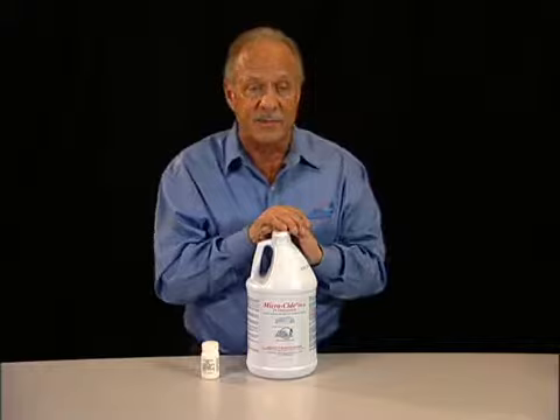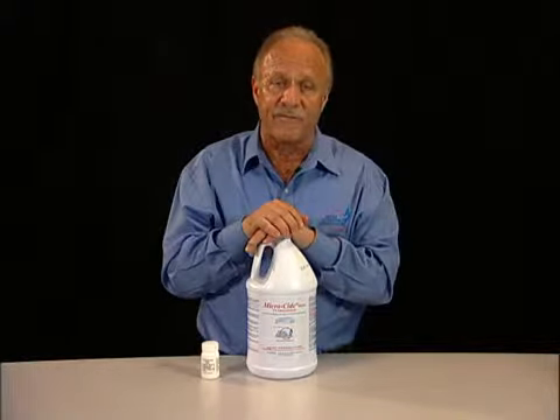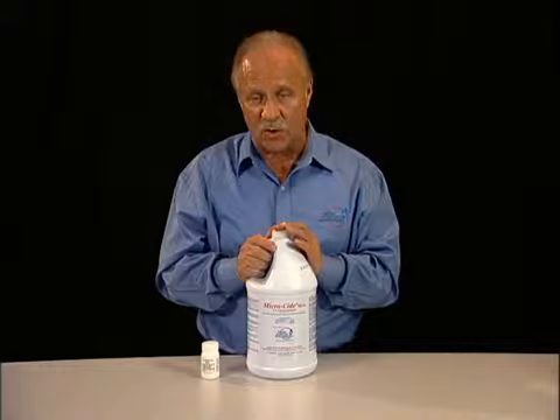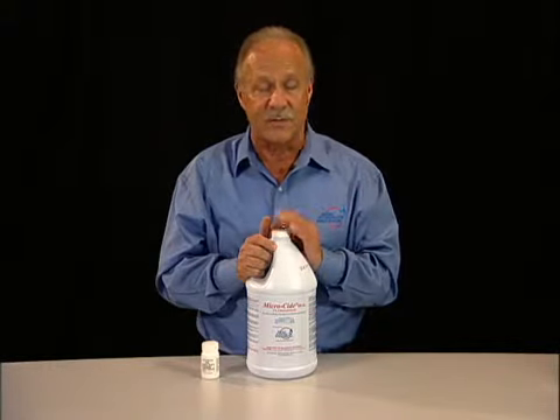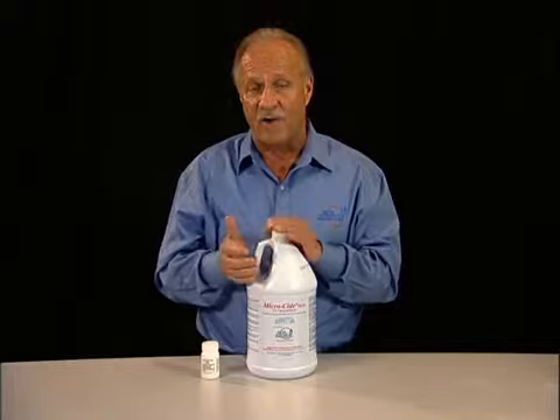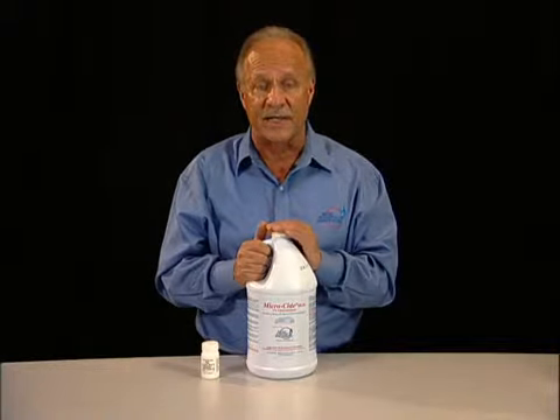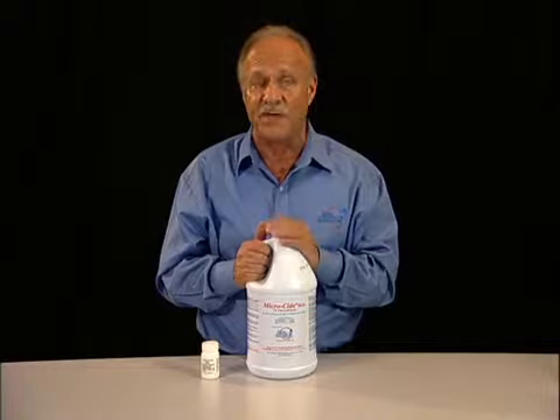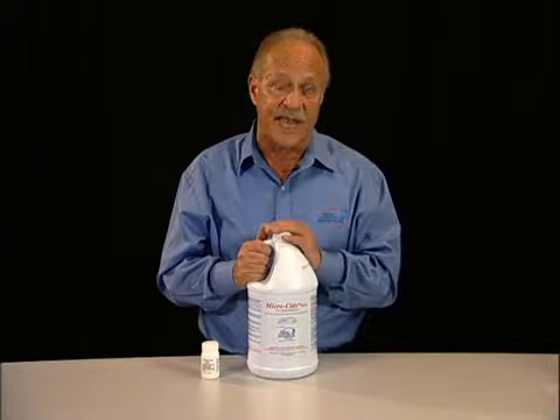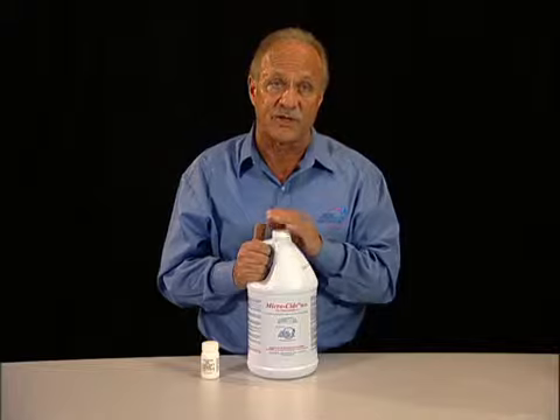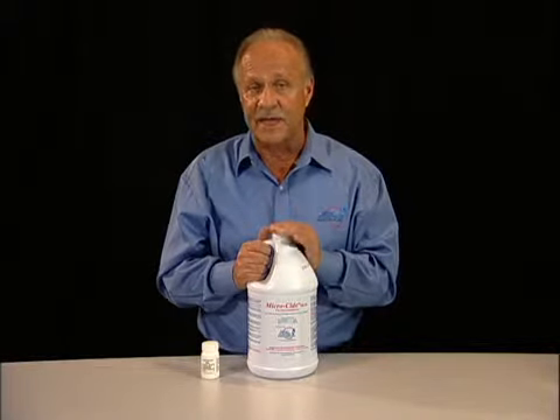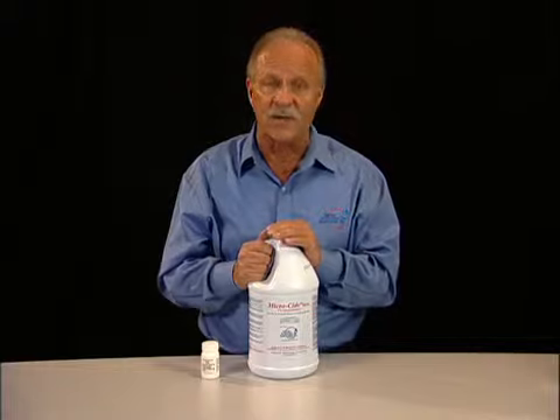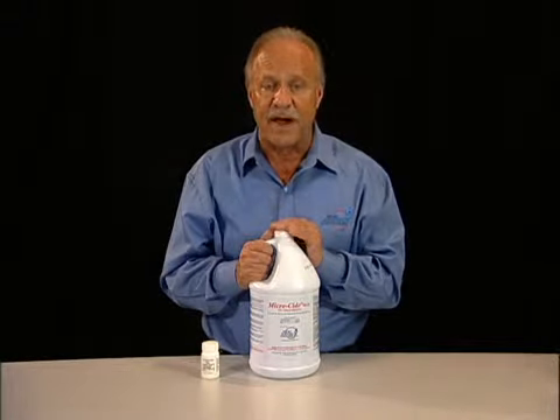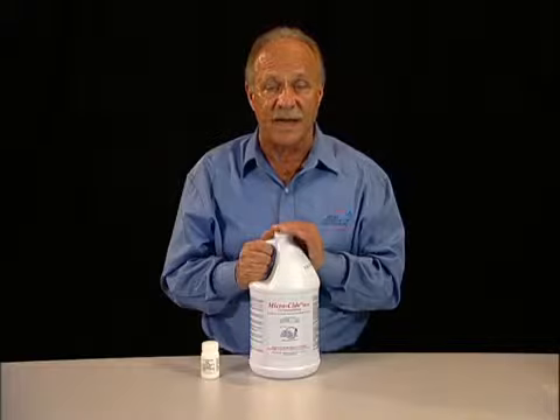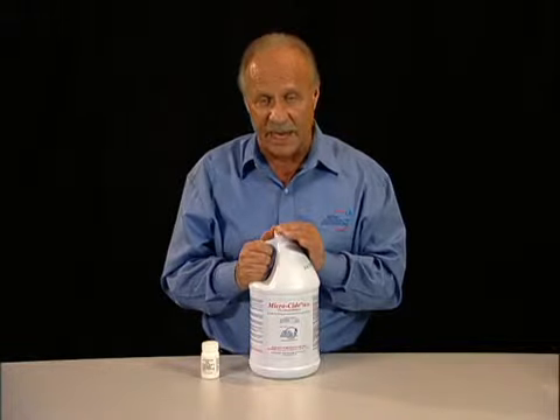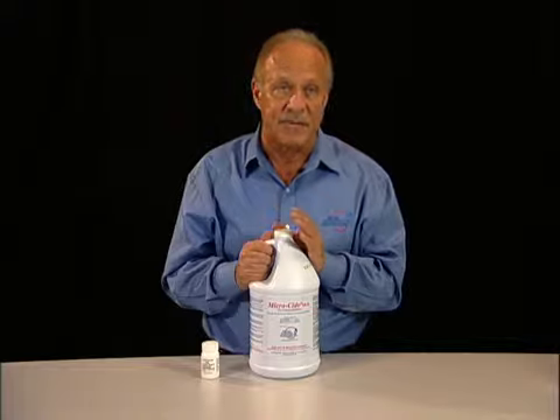Now, I know that some of the laboratories are simply using the products off-label and off-brand, and they're soaking the scopes and the related instruments in the solution for about 20 to 25 minutes. That's an off-label use of the product, which can create some problems in the event that a patient becomes infected and there's some sort of litigation, in that you haven't actually followed the instructions on the label of the product. The same thing goes with the Microcide product. The Microcide also requires a 45-minute soak time for the 14-day product, and their 28-day product requires a 90-minute soak time.